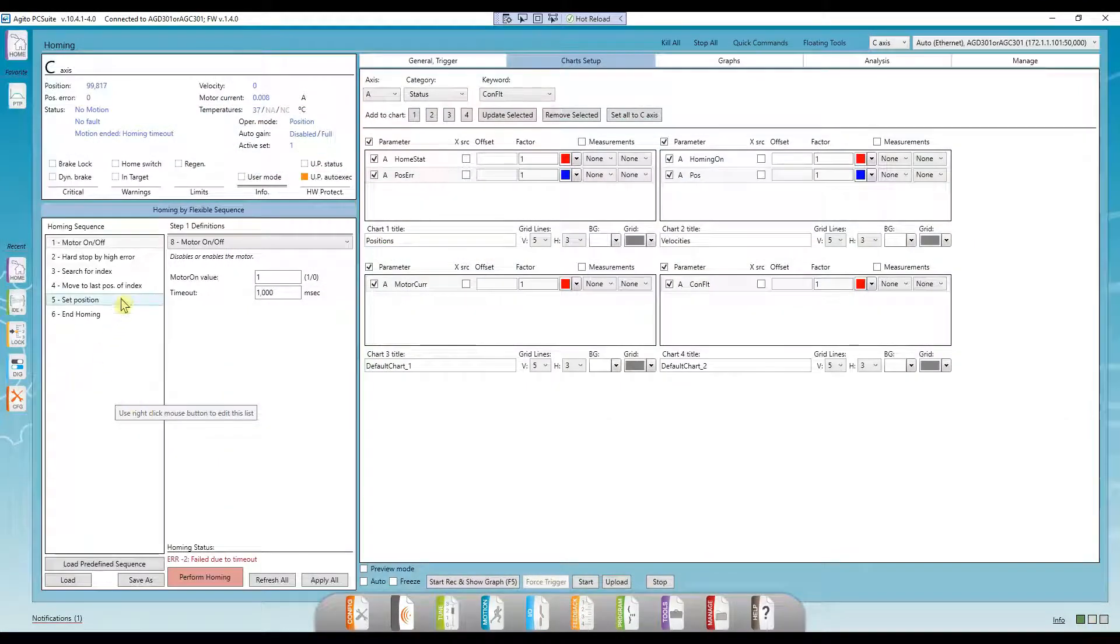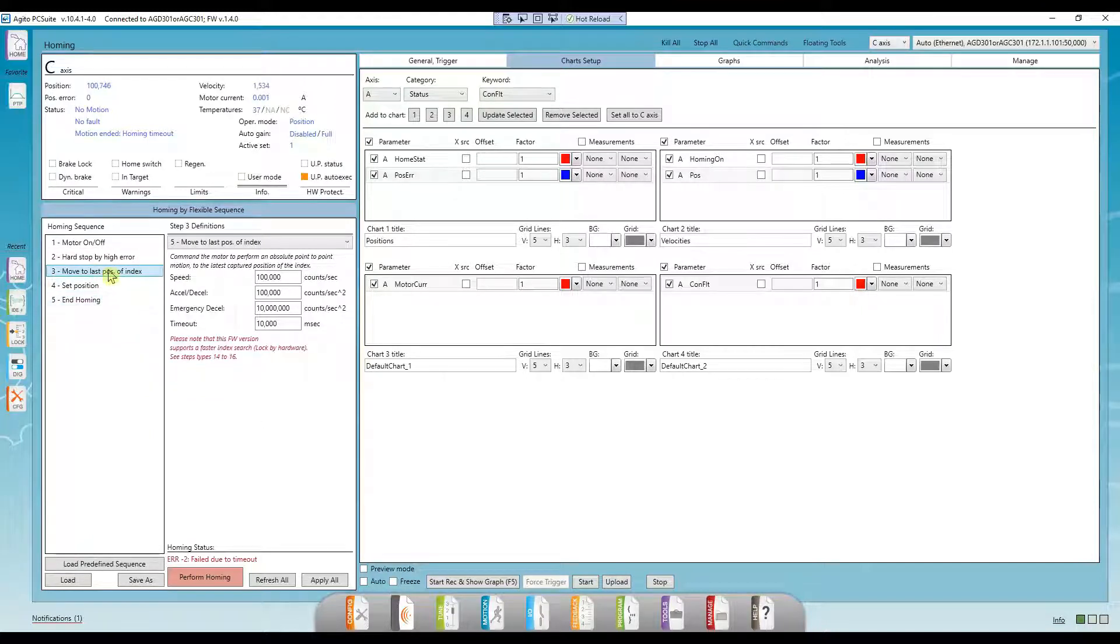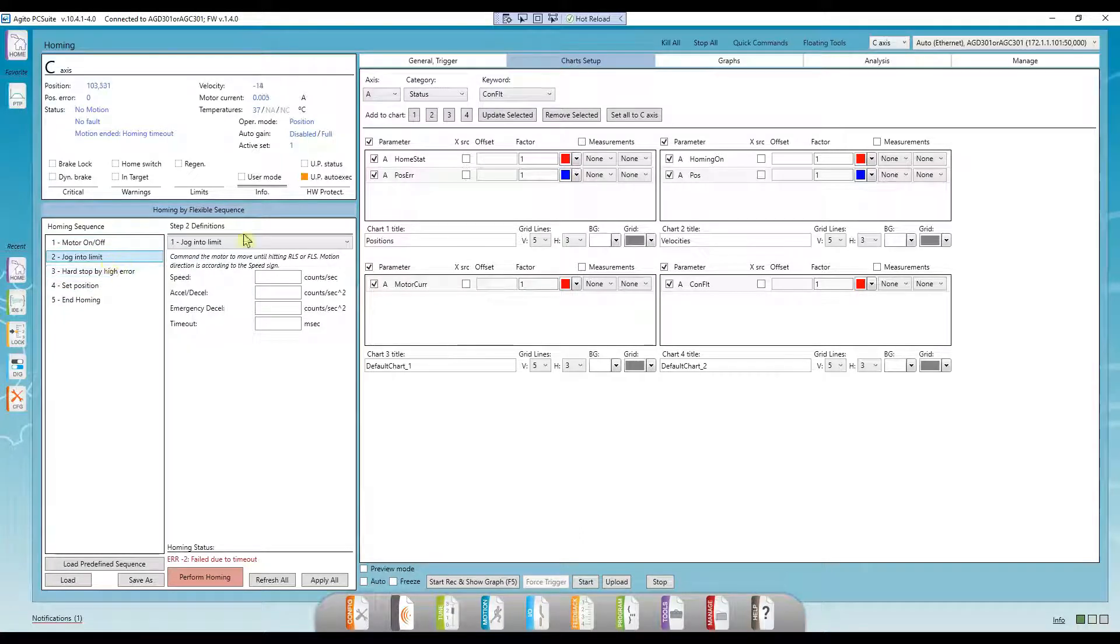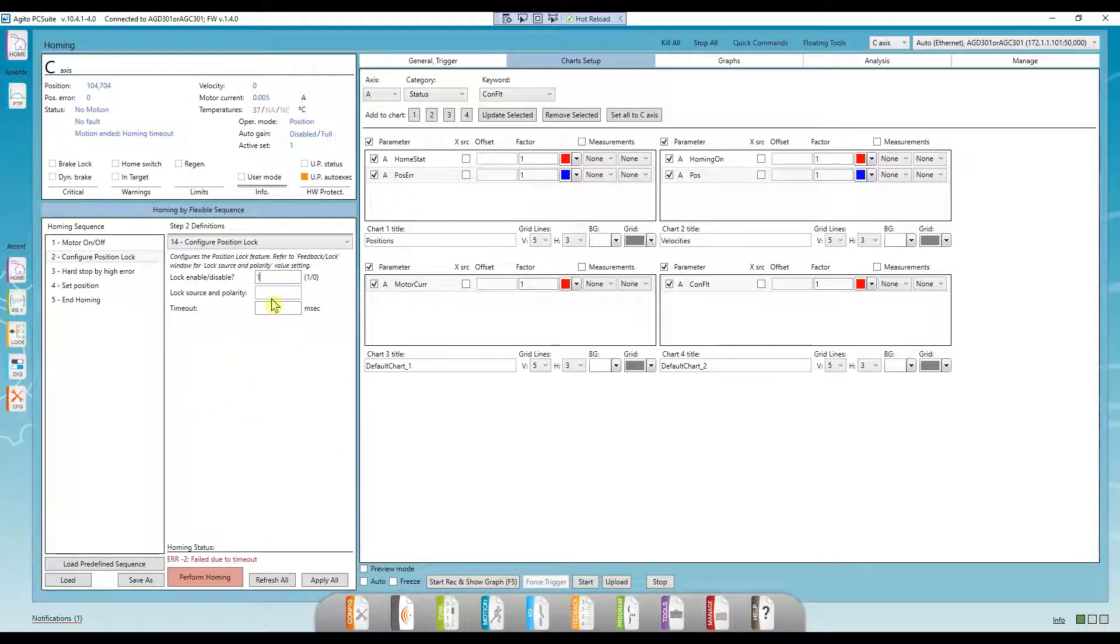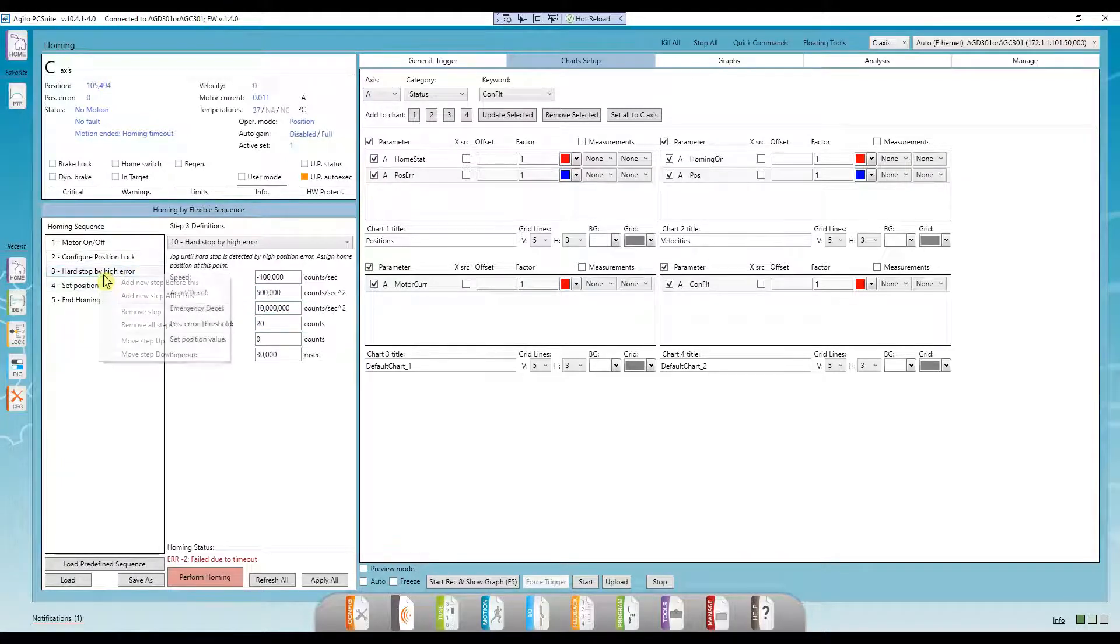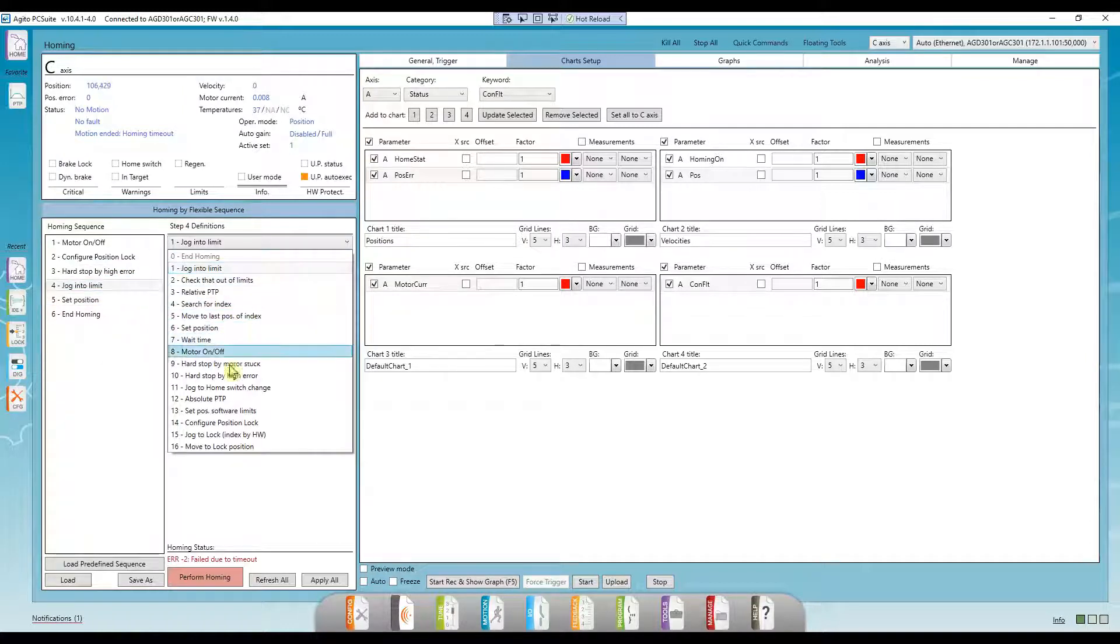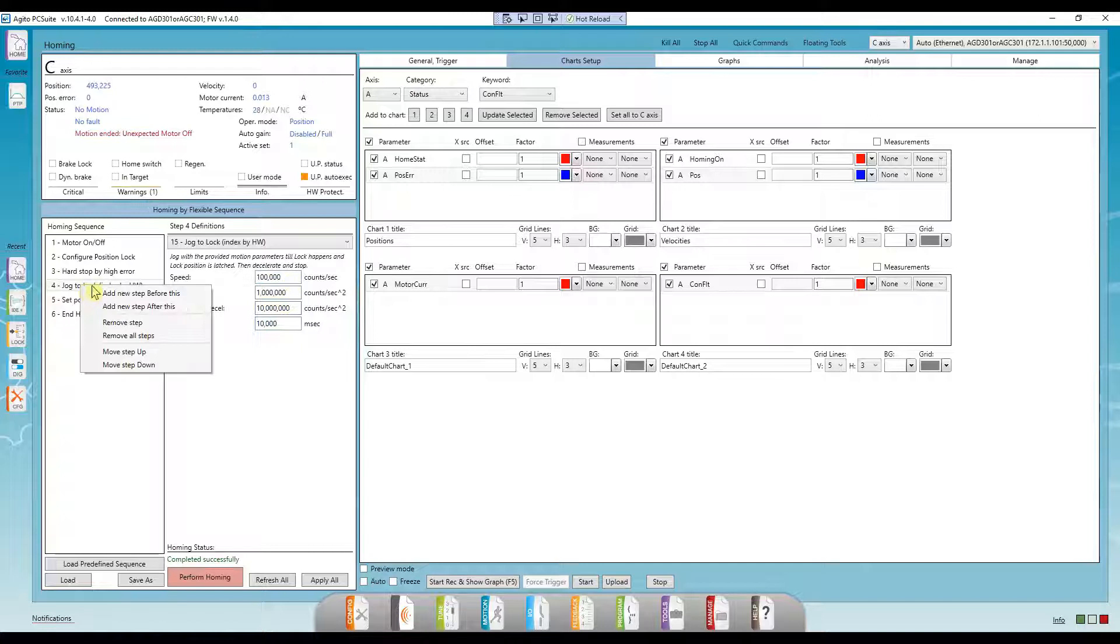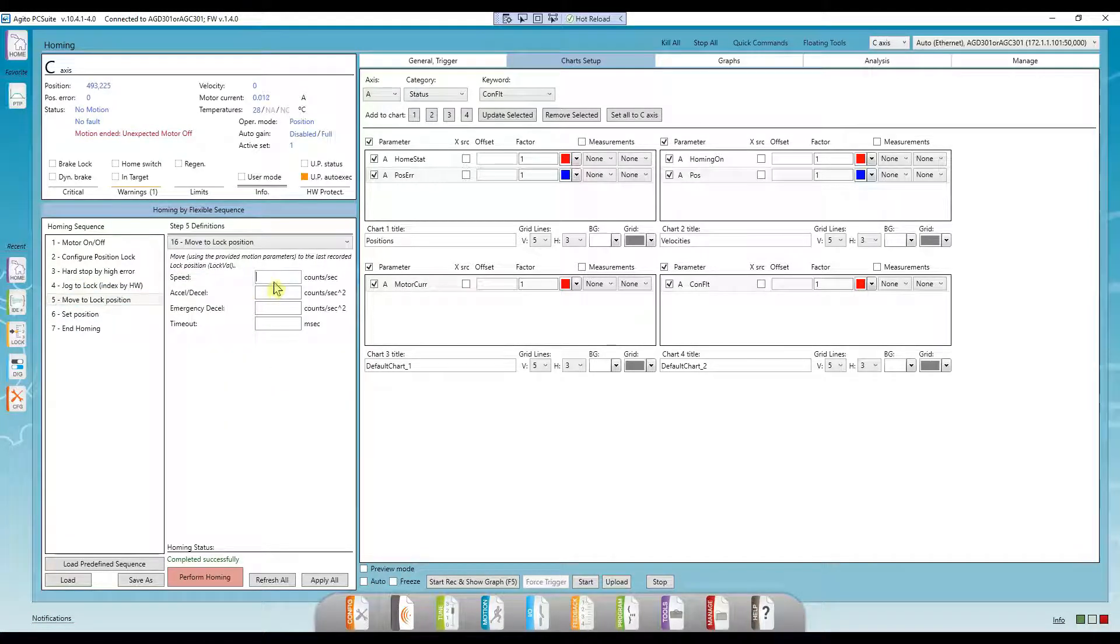Let's run another quick homing example, now using the position lock feature, so we'll be able to move at a much higher speed. I'll remove the steps relating to the index, and I'll add two new steps. First, I'll configure the position lock. I'm looking at the index mark of axis C with a normal polarity, which means I'll input the source as 30. Next, I'll add the jog to lock step and input a much higher speed than before. Now, let's run it.